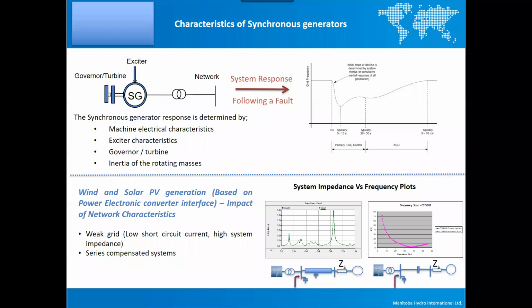You lose that when you connect generation using power electronics. You just lose that natural inertial response that you got from synchronous machines, and it's a challenge to deal with. So now people are talking about synthetic inertia. Synthetic inertia is all about trying to control the inverter and make it act as closely as possible to a synchronous machine, at least during disturbances. Conceptually it's easy, but making it work is challenging and needs a lot of engineering effort.